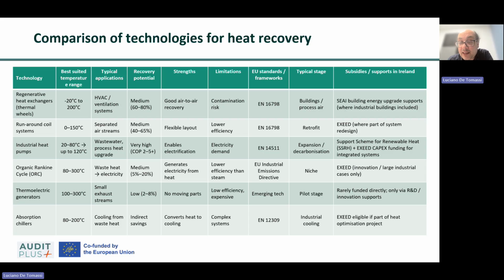Their main advantage is their ability to generate power from heat sources that are too cool for conventional steam turbine systems. Their principal limitation is relatively high capital cost, which means economic viability depends heavily on operating hours and electricity prices. ORC technology is commercially proven but remains less widespread than conventional heat recovery technologies. Support may be available through SEAI programs.